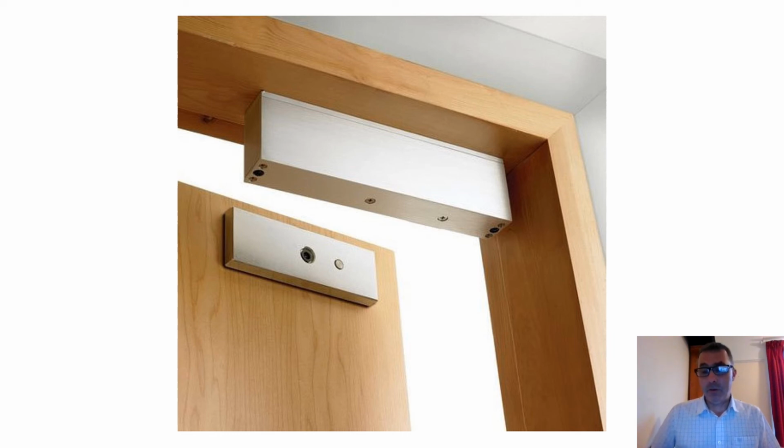People often will not use an interlock system on doors to theatres, so this would be a system where if you open the door, the laser automatically stops firing. That's not often considered safe in an operating theatre environment because you may be using the laser to control bleeding, for example, so you don't want that to stop if someone opens the door during the procedure.